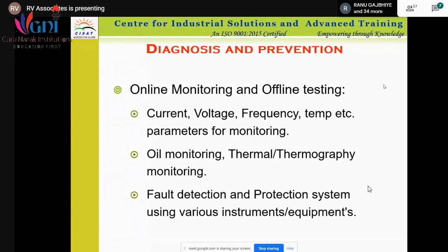Based on the oil quality and oil parameters, by doing this online monitoring we watch all the parameters in the oil, and based on that we diagnose what type of fault it will lead to, or what action is to be taken. So it is called predictive and preventive maintenance technique. It means you get to know in advance what type of fault will occur in the transformer, so you can stop the power supply and go for maintenance, so that heavy loss from failure of the equipment can be prevented.